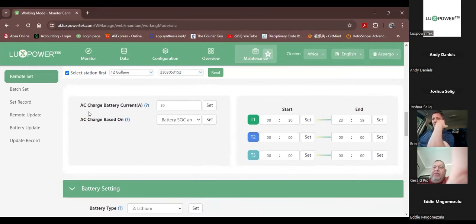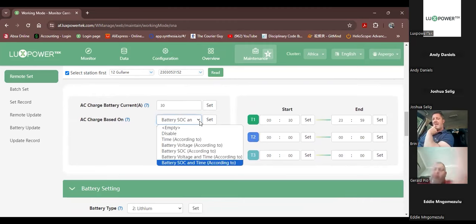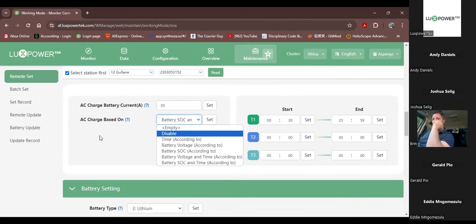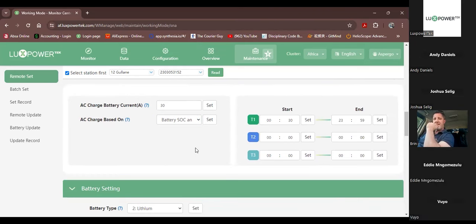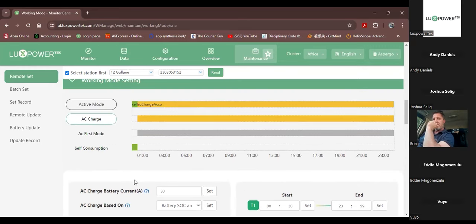All right, so here we have the battery AC charge current and the AC charge. If you look at these settings, there's nothing new about them. It's just that they've been grouped in certain areas. And here you can see that we've got the charge time set for 30 minutes after midnight, and the end time is 23:59. So this particular site runs for 31 minutes. Okay, so there's a minute there and there's 30 minutes here. It runs for 31 minutes on battery.